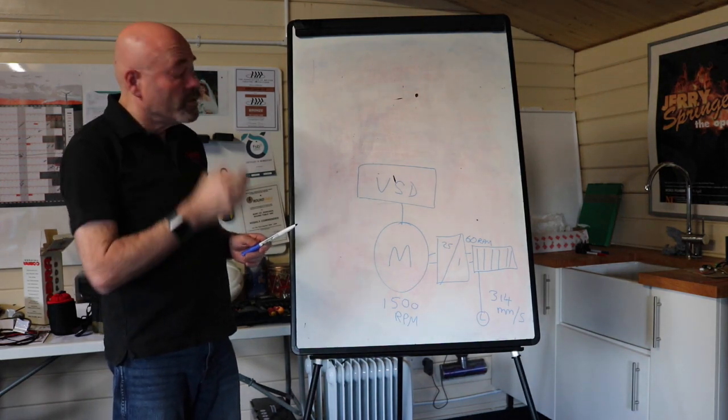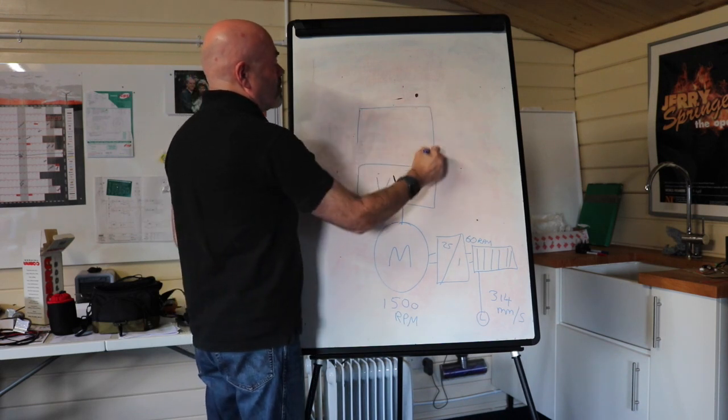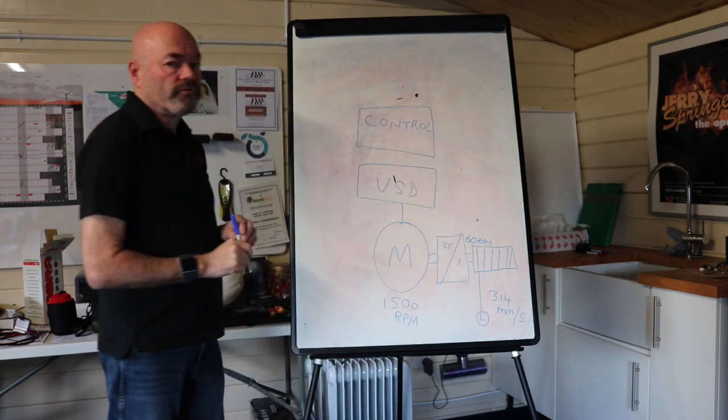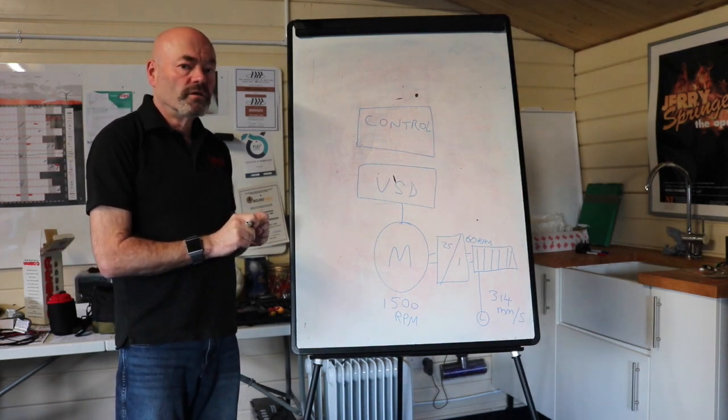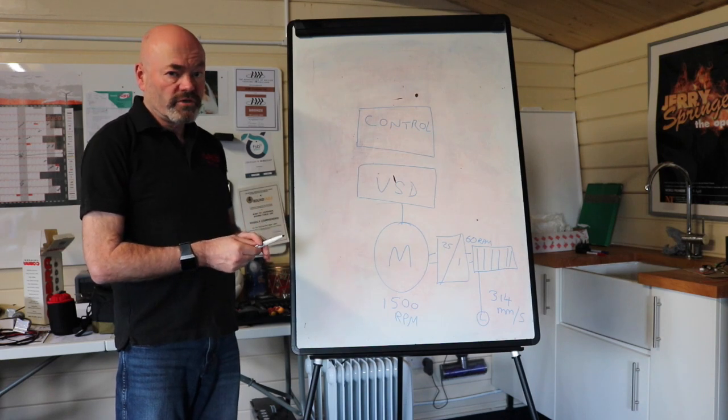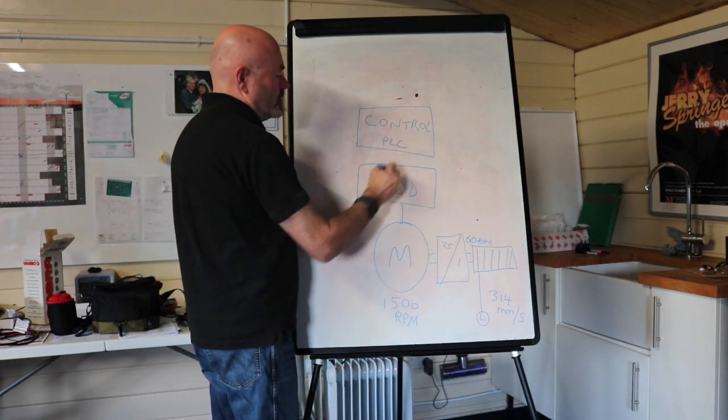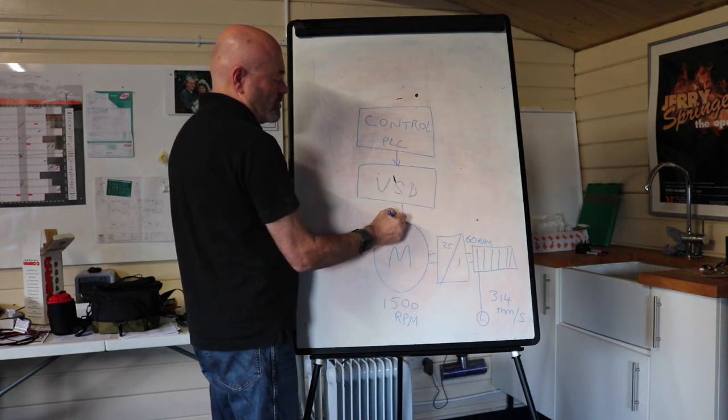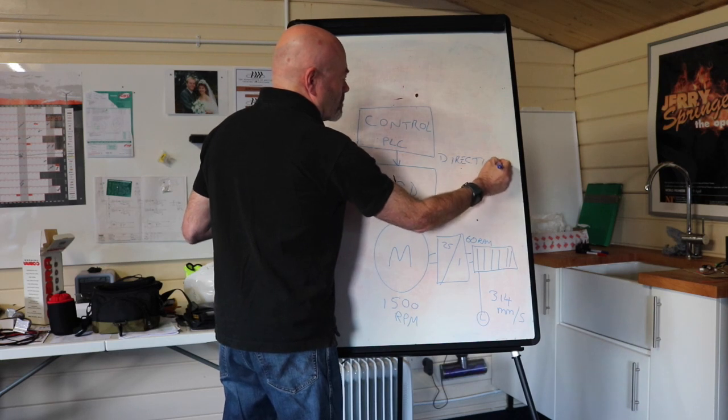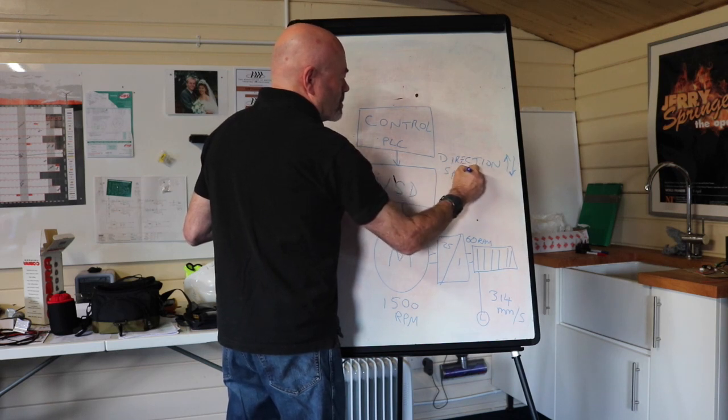And the variable speed drive needs to be given the information as to how fast it's got to travel and in which direction. So this will come from a control system. Now very often, that's a PLC, a programmable logic controller. Certainly AVW use PLCs, many of the other automation suppliers use PLCs. The alternative would be some dedicated hardware, motion control hardware. So the PLC has to give the variable speed drive its information. The information being direction, in this case up or down and speed.